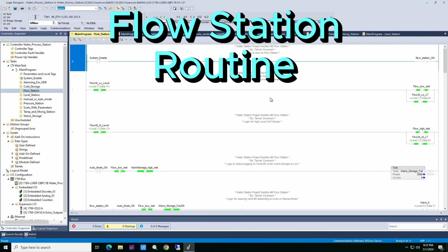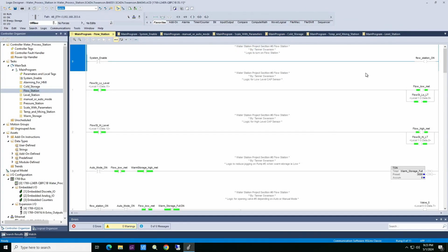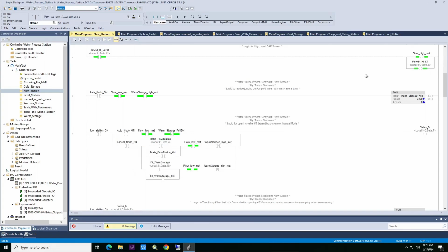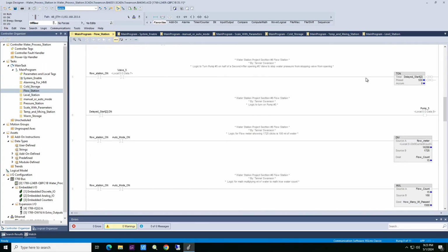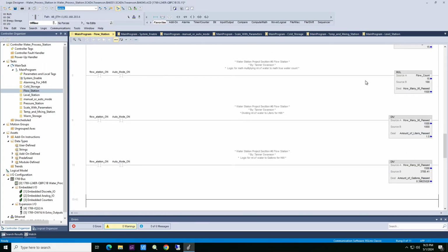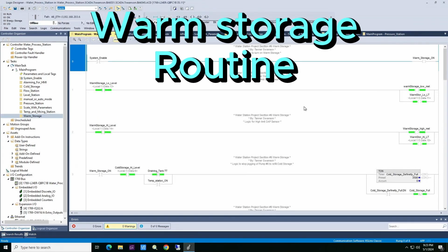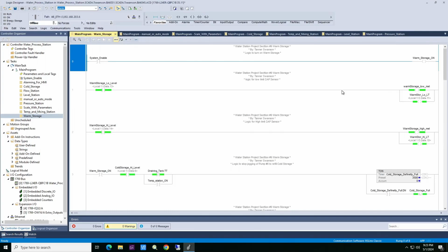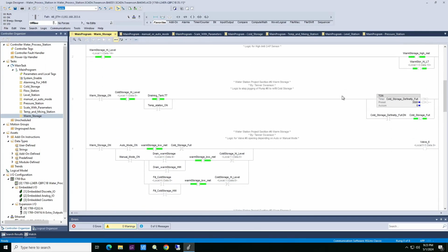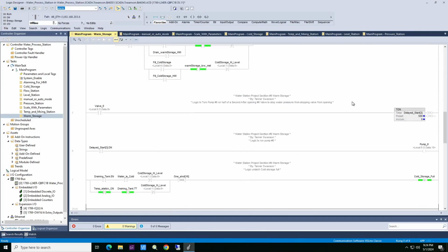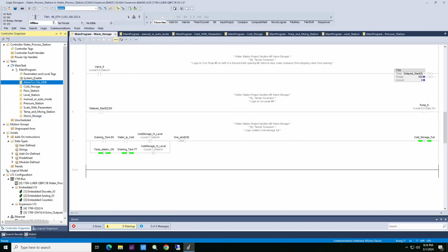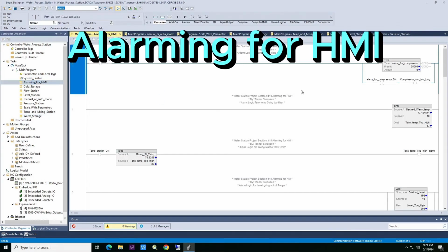Here is my flow station routine. At the bottom, I have math bits to show the difference between liters and gallons and mass produced for the final product made. Here's my warm storage routine, to make sure that the cold storage is full and the latch is closed if it's circulating water with the compressor. And then here are all my alarming for my HMI.